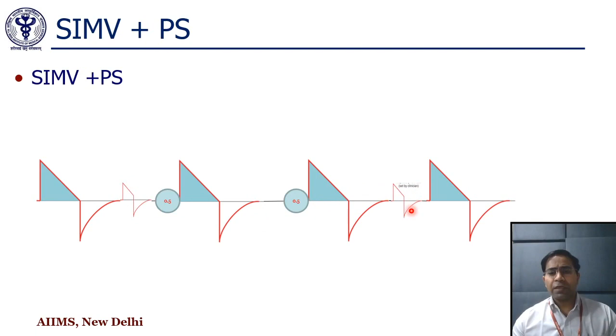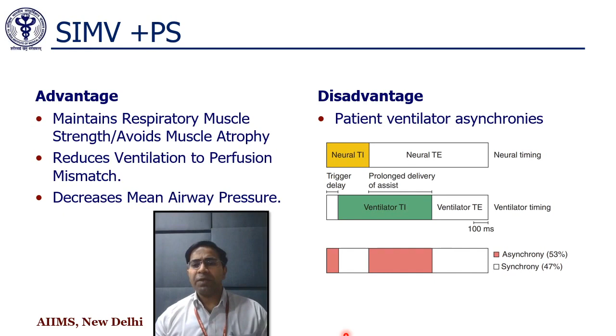Coming to SIMV with pressure support, advantages and disadvantages. Advantages are it maintains respiratory muscle strength, avoids muscle atrophy, reduces ventilation to perfusion mismatch, and decreases mean airway pressure. But it is also associated with certain disadvantages like patient ventilator asynchrony. Say we set a pressure support of 10 and a respiratory rate of 10 with an I:E ratio of 1:2. The patient will spend some 2 seconds for inspiration, and some other amount of time during inspiration when the patient is on pressure support. So the neural inspiratory time will keep on changing from A to B, and that leads to confusion. The patient is breathing for some neural inspiratory time when on pressure support, and for some other time when on IMV, and that leads to ventilator asynchrony.